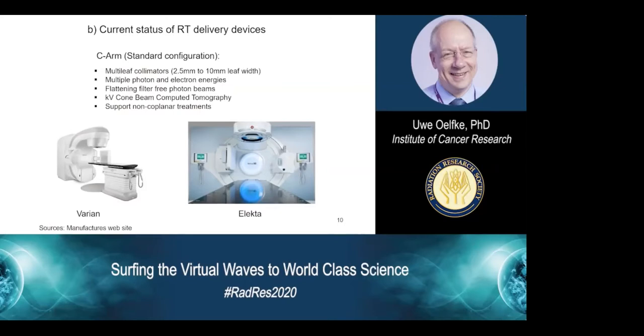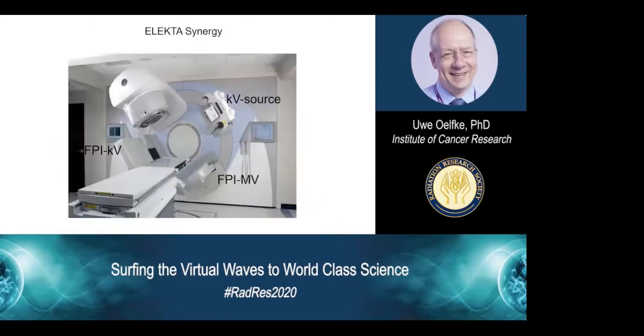You see here two standard machines, a TrueBeam from Varian and a Versa HD from Elekta, and they have the standard configurations: a multi-leaf collimator for shaping the radiation fields, multiple photon and electron energies, flattening filter-free photon beams, and then for image guidance, a kV cone beam CT. So you see here an X-ray source and a flat panel detector, and if the gantry is rotating, you can acquire CT images of the patient directly prior to treatment.